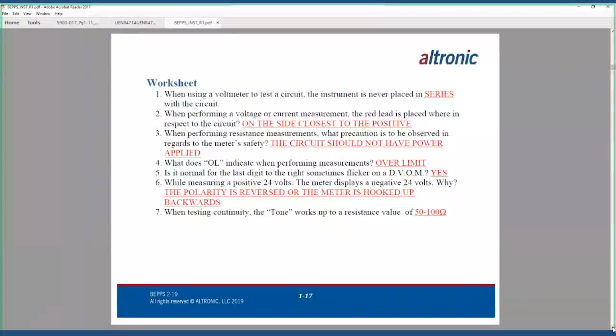While measuring a positive 24 volts, the meter displays a negative 24 volts. Why? We covered that one. The polarity is reversed or the meter's hooked up backwards. So again, the positive probe of your meter is expecting to see a positive voltage signal, and the black probe is expecting to see a negative voltage signal. So that is a good point. By going through this, not only could your meter maybe be backwards, but if your meter's right, then maybe somebody hooked up the batteries wrong. I've seen that happen a few times.